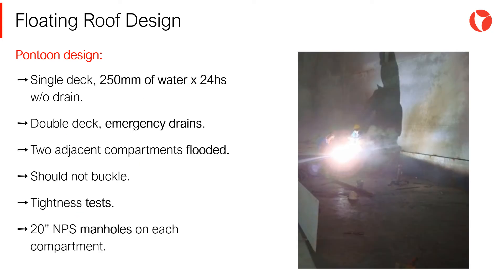The design of the pontoon must comply with the requirements of Annex C of the API 650 code. Some of the main requirements are: single deck roofs will be designed to stay afloat with a load of 250 mm of water on the central deck during 24 hours — this is without drain. Floating roofs must stay afloat with two adjacent compartments flooded. Each compartment will have a 20-inch nominal pipe size manhole for inspection.